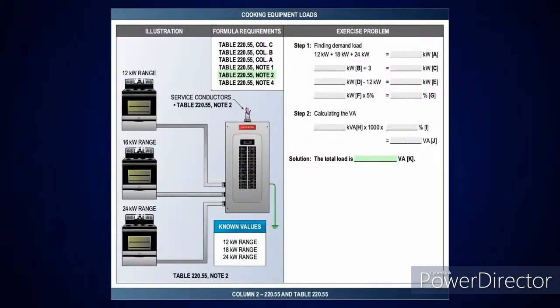Okay? Nice. And then here, same thing, 12, 16, 24. Add them all up, get an average rating, subtract 12, then you take each additional kilowatt rating there at 5%, and then add it up based on those 3 ranges, which again would be 14 kW based on column C. Okay.